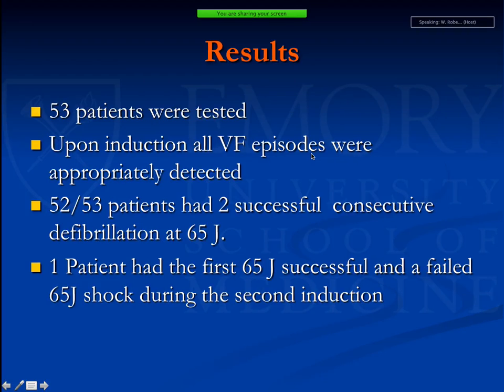And basically the results of this study were encouraging as a first study. 53 patients had DFT testing, so they induced VF. Upon induction, all VF episodes were appropriately detected. 52 out of 53 patients had 2 successful consecutive DFT. In the old days, devices used to be tested twice and 3 times because this is a probabilistic phenomenon, so you have to make sure it will work every time. And 1 patient had the first 65 joule successful, failed the second 65 joule, but ended up having an 80 joule successful shock.